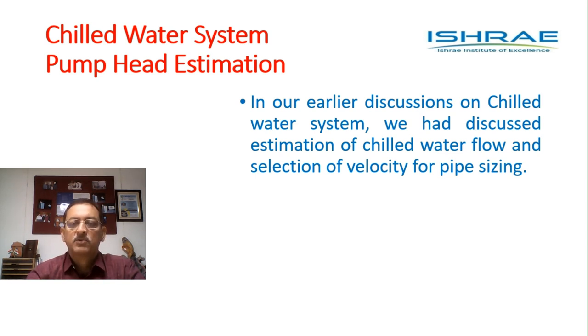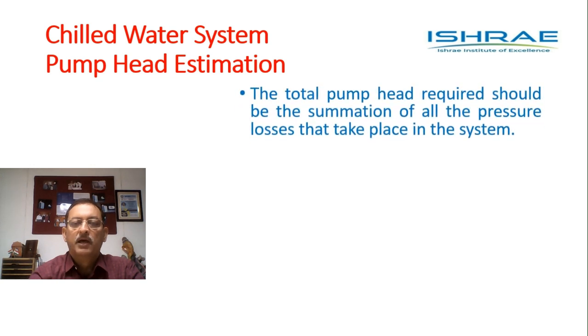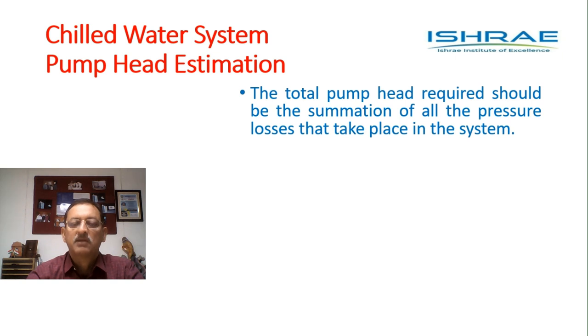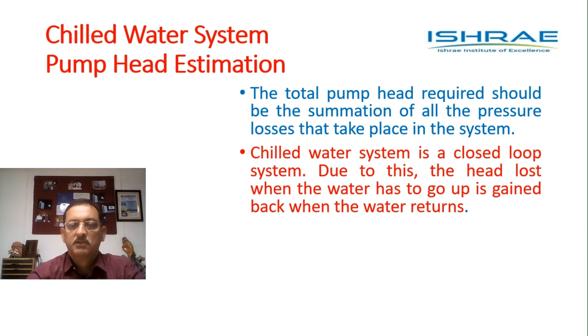In our previous discussions on chilled water systems, we had discussed estimation of chilled water flow and selection of velocity for pipe sizing. This video comes after that and falls naturally in the series. This video is about chilled water pump head estimation. The total pump head required in the system should equal the summation of all the pressure losses that take place in the system.